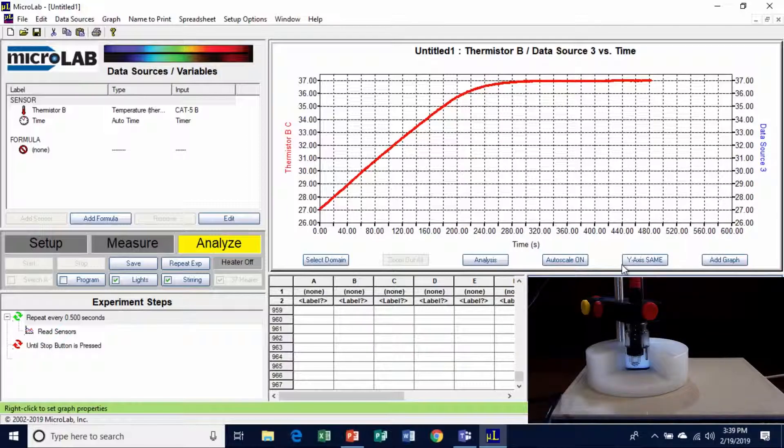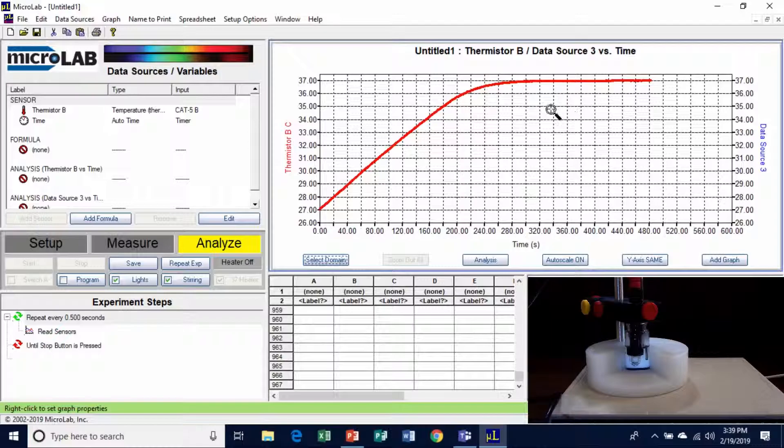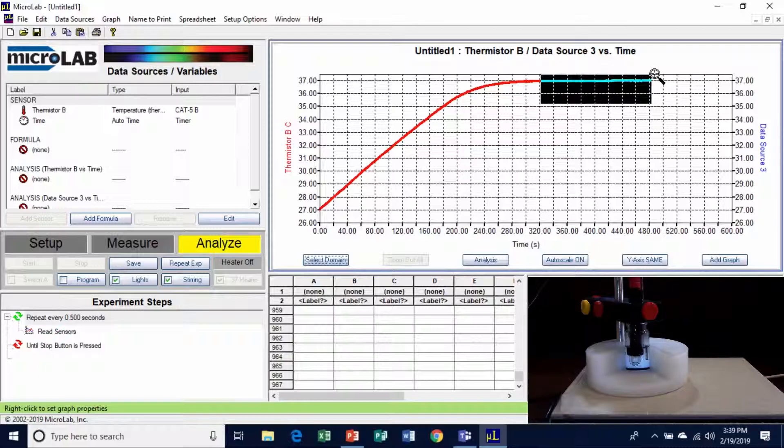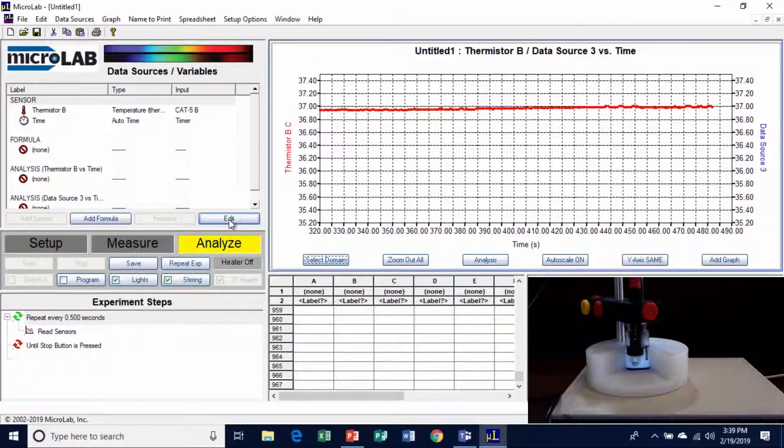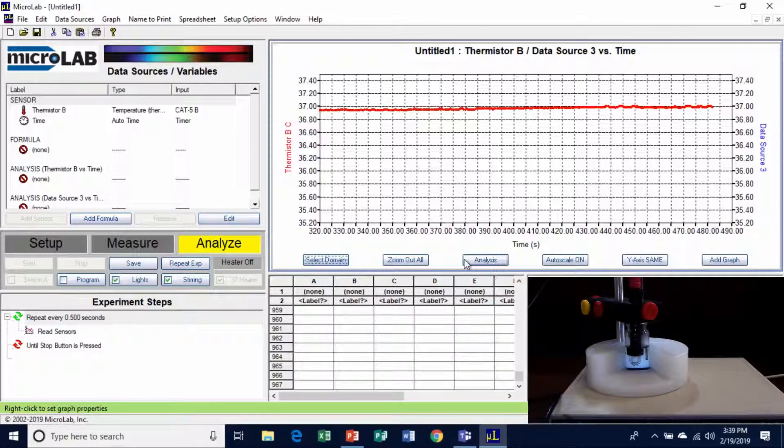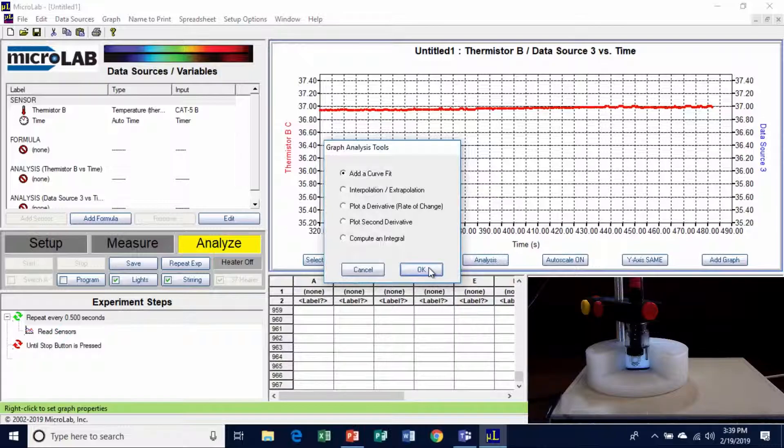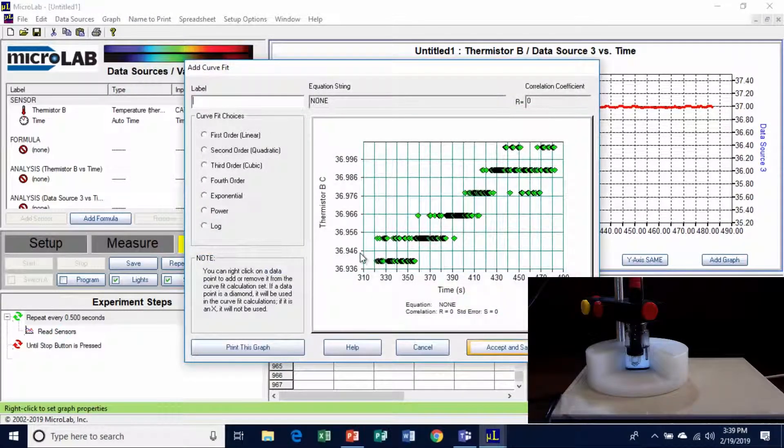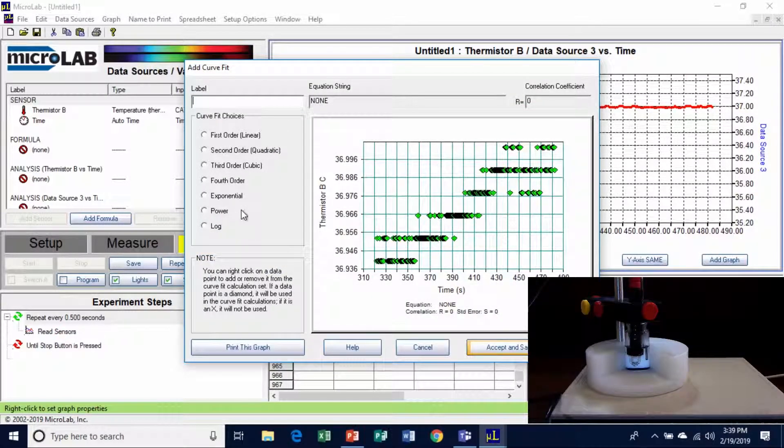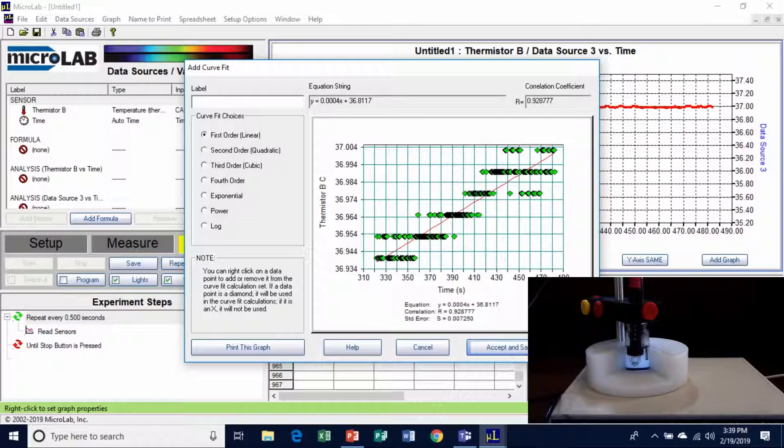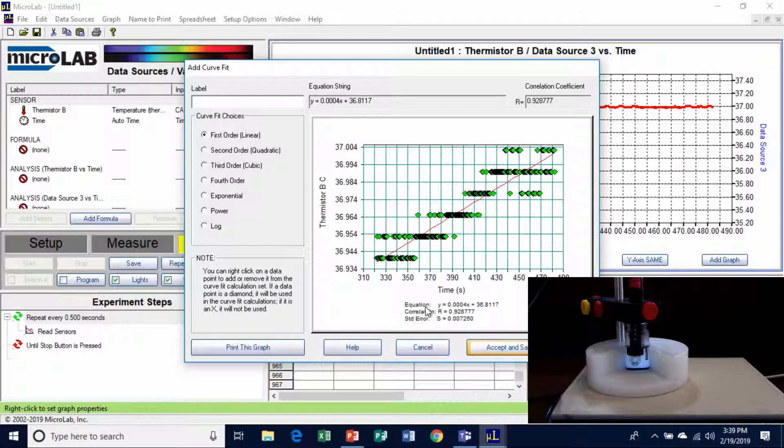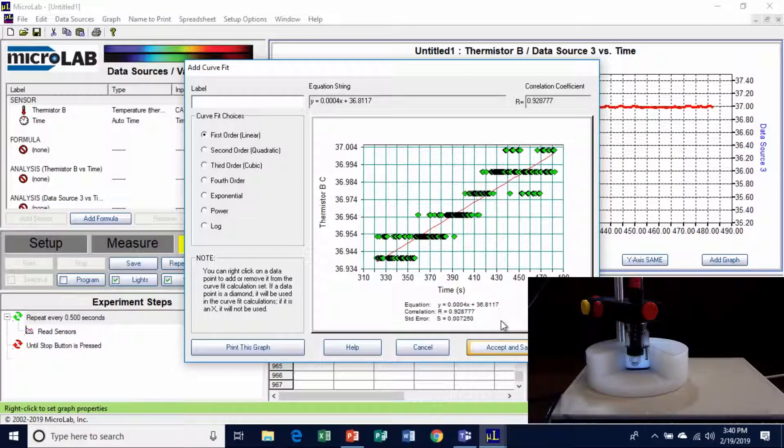Now what I'd like to do next is just select a domain on this and we're going to do two kinds of analysis. I'm going to start at 320 seconds and I'm going to just draw a box here around the data. And if you look at that, boy, that's pretty darn flat. I'm going to run a curve fit through that. And it's time and temperature and I'll say okay. And I want to, wow, it looks like it's drifting up just a little bit. I'm going to put a first order line on it. It's pretty much straight. But look at the slope. The slope is right here. It's 0.0004 degrees per second. So basically it's constant.